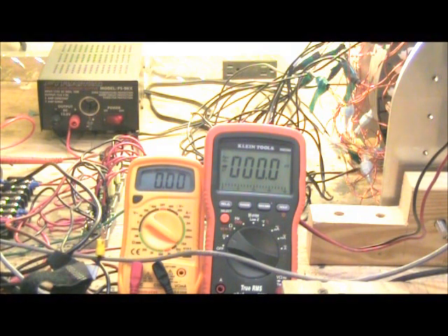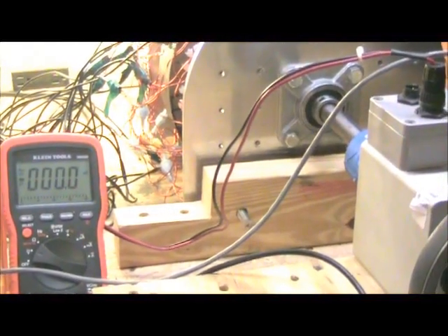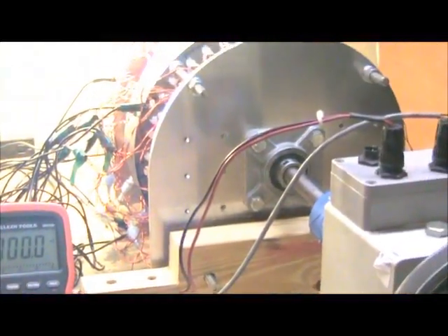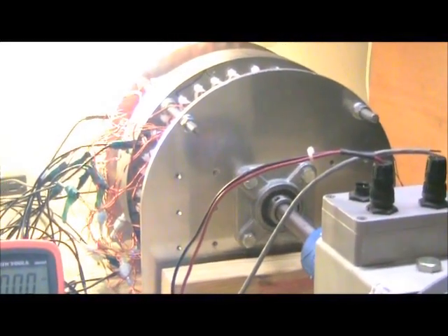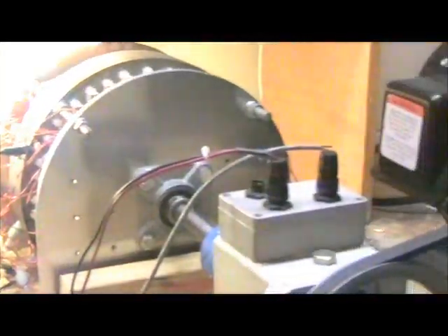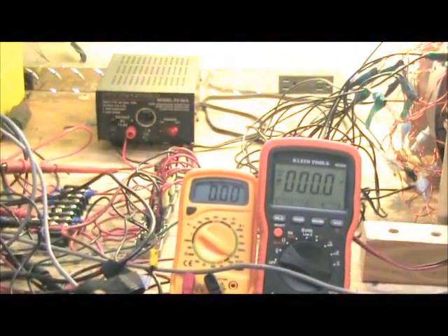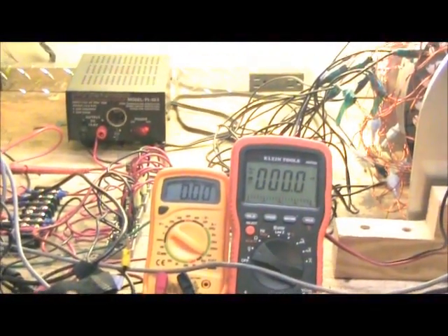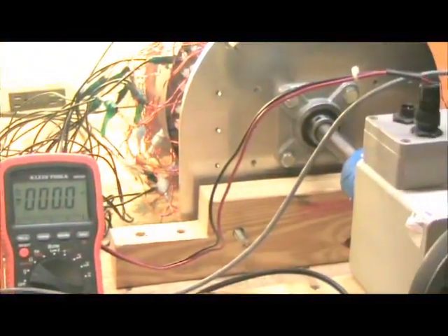This is the latest generator. It's designed to run at 2400 RPM and it puts out easily 10 kW. But this little setup here—this three horse motor—cannot handle that generator, and we can only get it up to like 2200-2300 watts before the drive kicks in. The limiting factor is the drive and the motor.